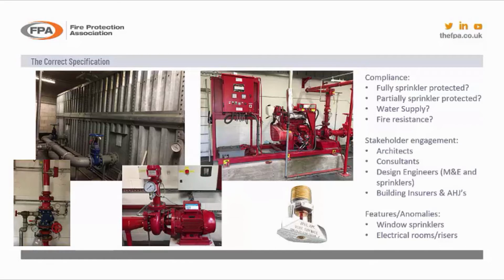Water supply. Due to spatial limitations, these are normally compromised on the ability to store the correct quantity of water to suit the hazard classification and the height of the building. Water supplies are normally compromised because space is at a premium. Lots of office tower blocks have water supply capacities reduced and hope that the infill from the town's main can make up the difference, because they are stuck by the structural elements of the building and they're normally put down in basements. So has the water supply been compromised?